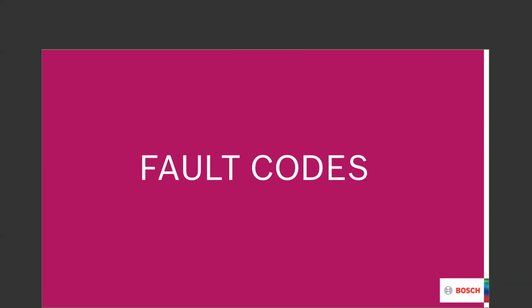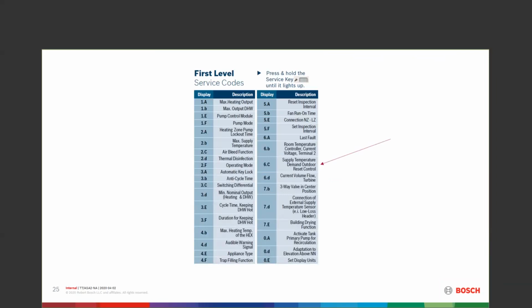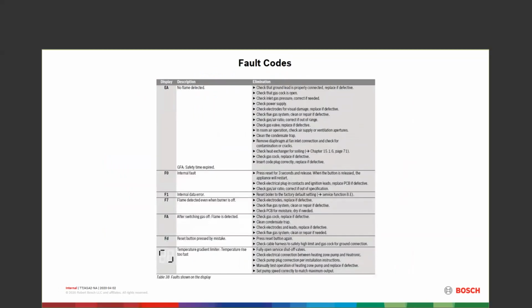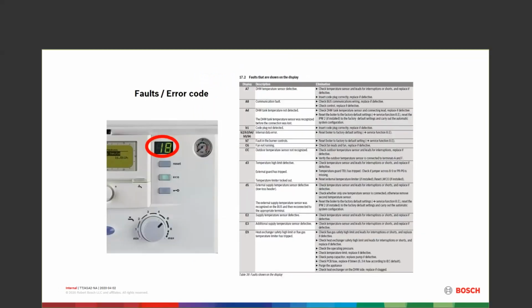We're going into a little bit about fault codes and what shows what's there. One of the things that I use all the time is the latest fault. What was your last fault code? A lot of times people don't know it's been reset, turned off, turned back on, and now it's running. This will give you what that last fault was. So whether it's EA or E9 or D5 or D3, whatever that fault code might be, that's what's going to show up there. And it only stores one, so it's a single fault code. Too many slides.